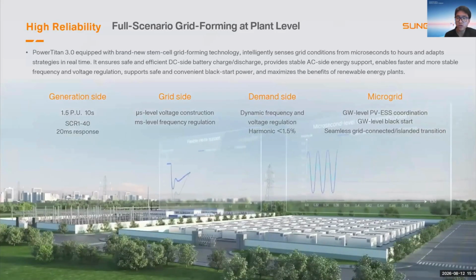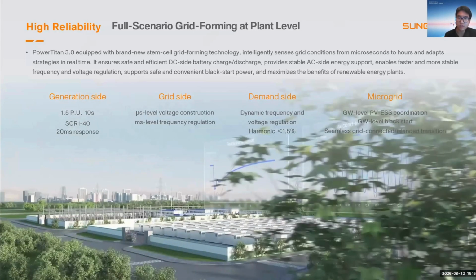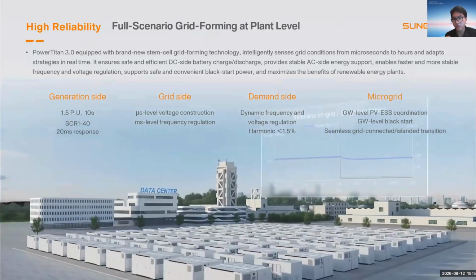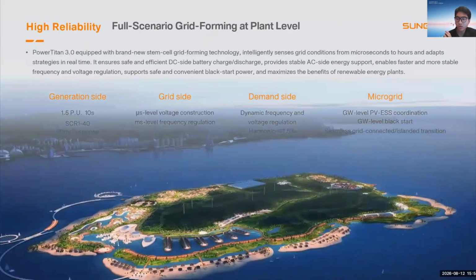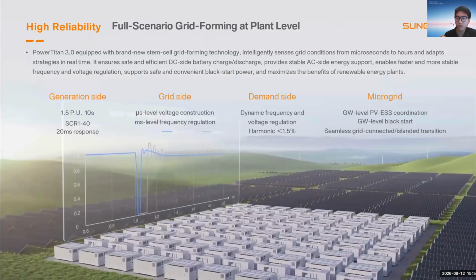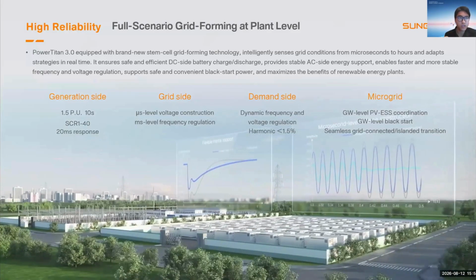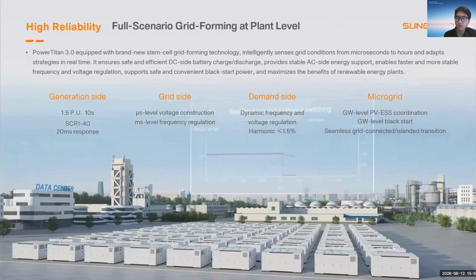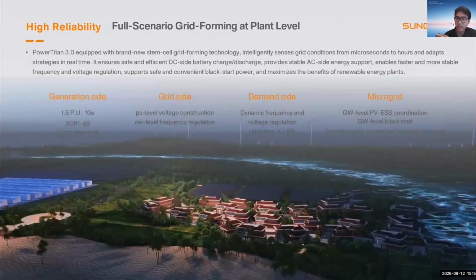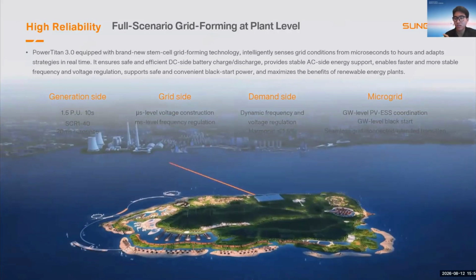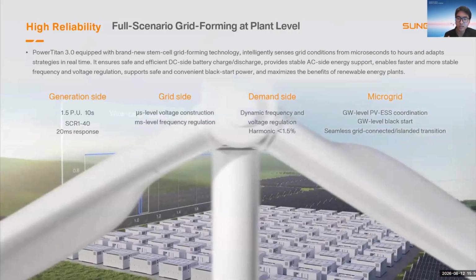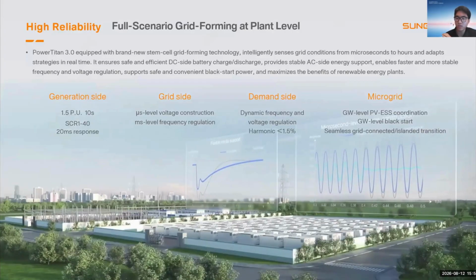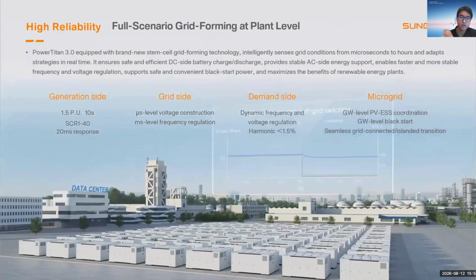And finally, I would like to talk about grid adaptability, which is becoming more and more important as renewable penetration continues to rise worldwide. Therefore, an energy storage system should not only be able to absorb green energy, but also be able to actively support the grid. As early as 2021, Sungrow proposed the concept of grid-forming technology through AI-based grid condition sensing, PV and storage coordination, and grid forming control. We are able to inject system-level stability into renewable power plants and ensure grid stability under all operation scenarios, from the generation side, grid side, demand side, or even microgrid.